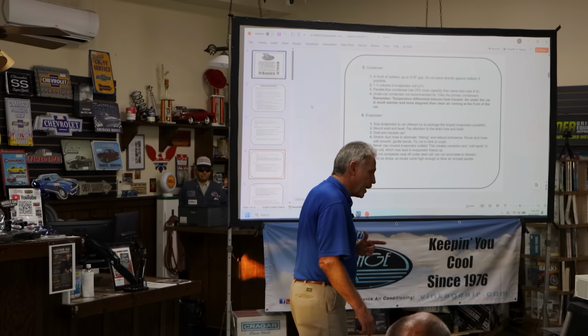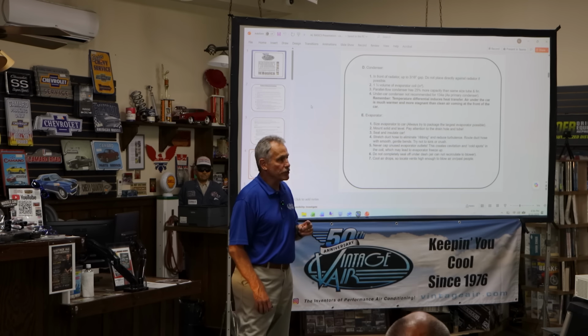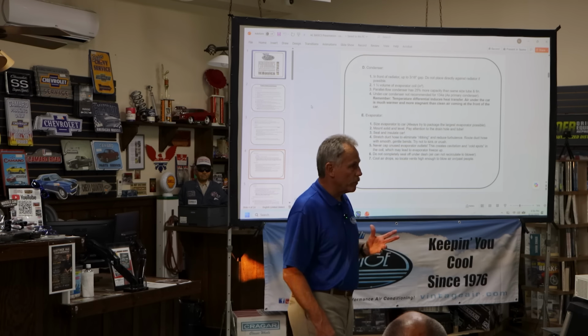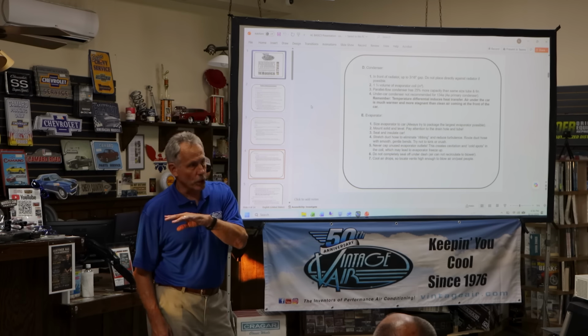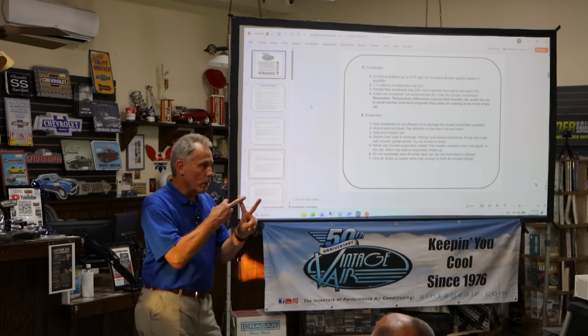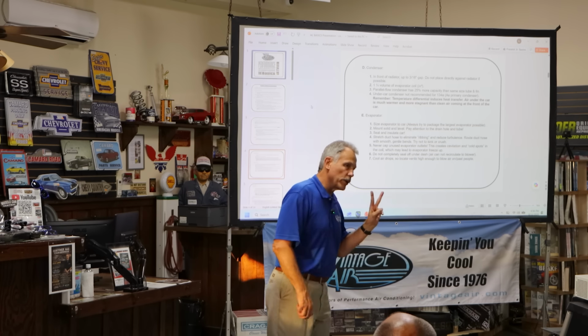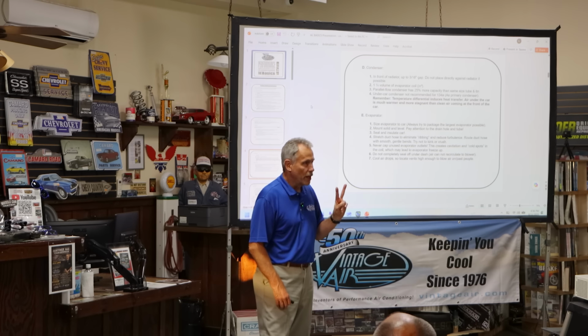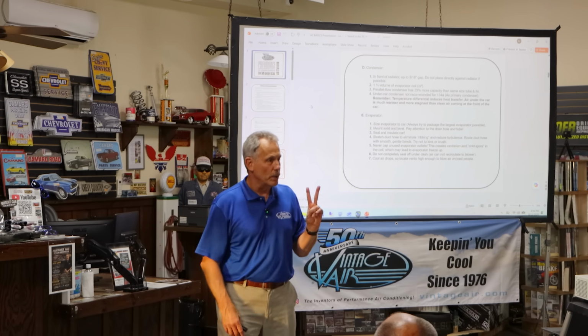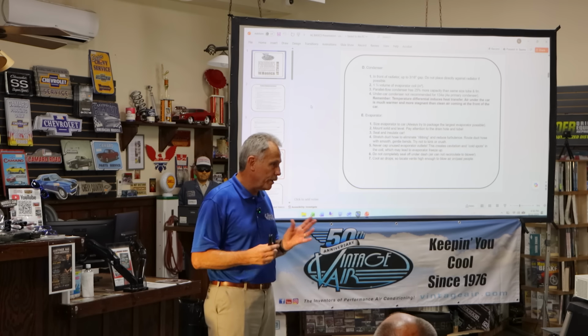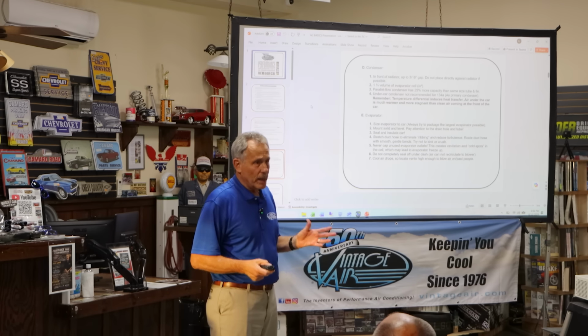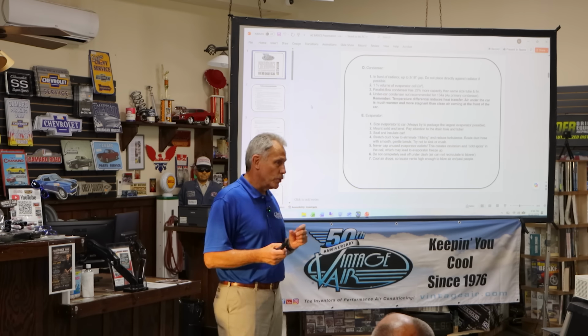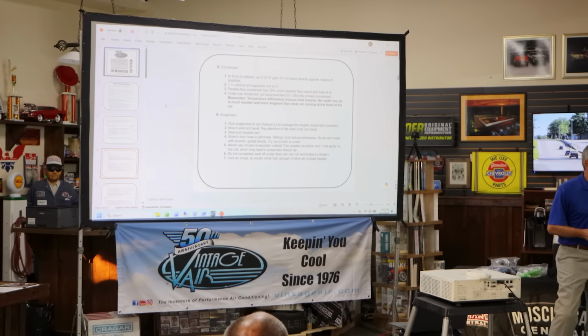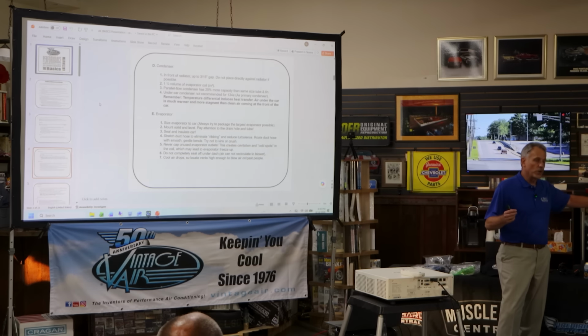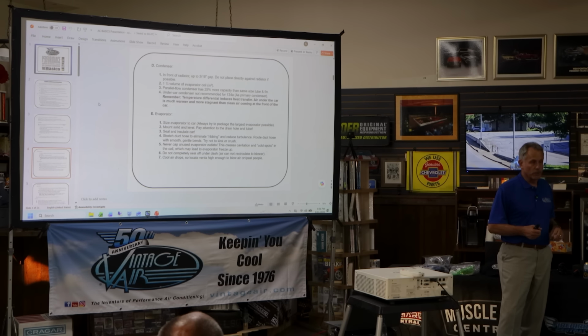When we're talking about charging, before you charge a system it has to be evacuated, right? Y'all probably heard that. You have to evacuate the system before you charge it. Evacuation does two things. Number one, it pulls the air out of the system. But the more important thing evacuation does is it puts the system under a vacuum, 30 inches of vacuum. By doing that, you lower the boiling point of water. So when you're doing installations here, similar to what we are, it's very humid. When you're building your AC hoses and putting them on, you've got humid air in there. So you want to make sure you evacuate that system properly and boil that moisture out, because that'll degrade performance of the system if you have moisture in there.